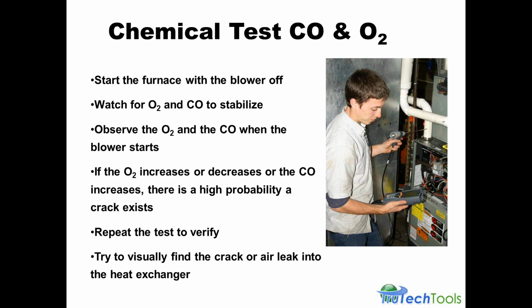And this would warrant further examination, and perhaps visually trying to find the crack or the leak in the heat exchanger. We do sell a book at TruTech called the Furnace Examination Guide. It's also called the Heat Exchanger book. It has in it all major makes and models from North America of the common failure points for cracks or leaks in heat exchangers. And like a lot of things tend to, when they do fail, they fail in the same area, and this book compiles them all. So that's a good thing.